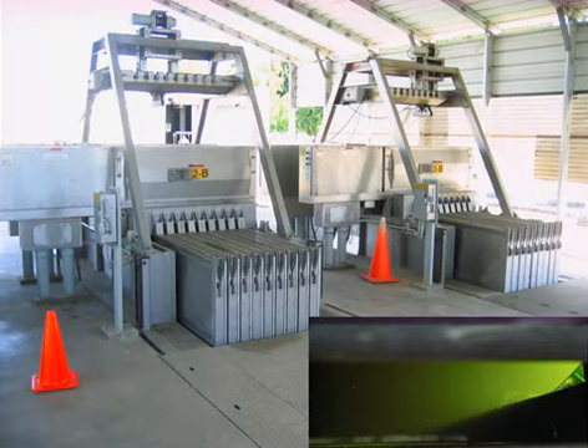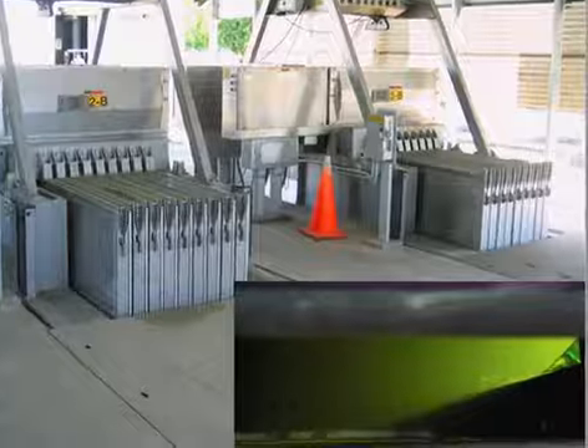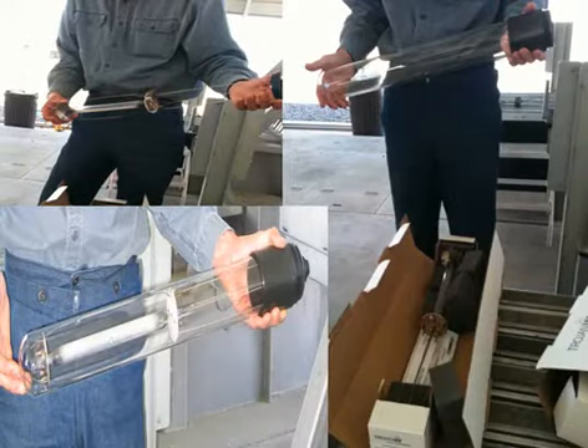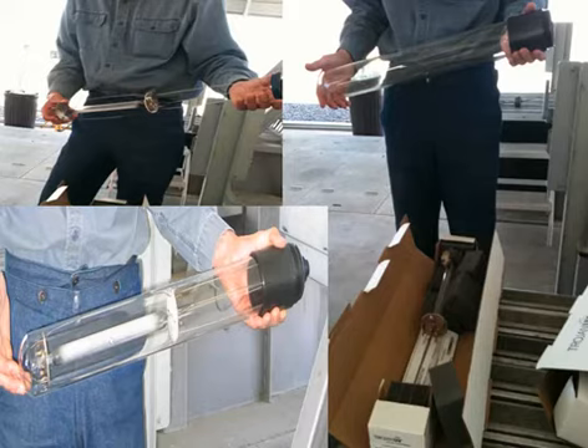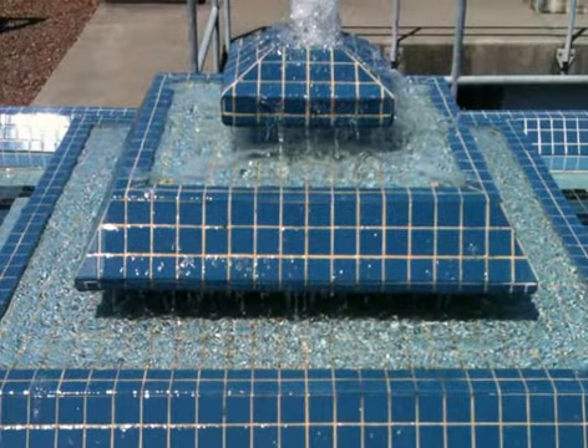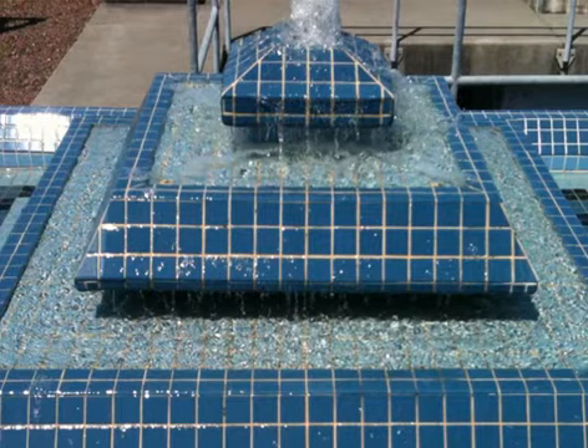In the disinfection area, ultraviolet light destroys the DNA of the bacteria and viruses, thereby eliminating the means of their reproduction. This expensive light bulb is for the UV treatment. It has an operational lifetime of 10,000 hours. The water has to pass within 2.5 inches from the UV light in order to destroy the DNA material. The fountain represents the clean water generated after passing through all the steps of the treatment plant.